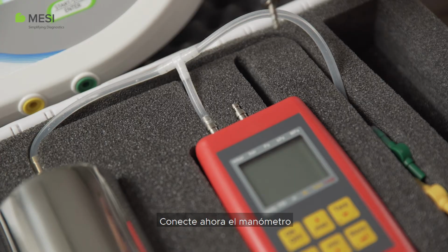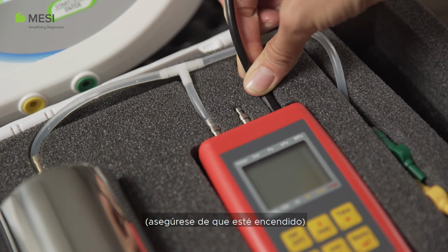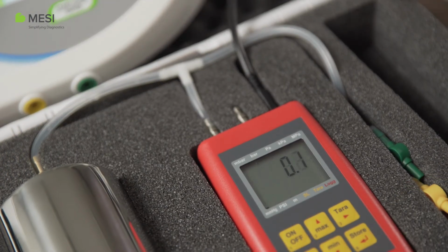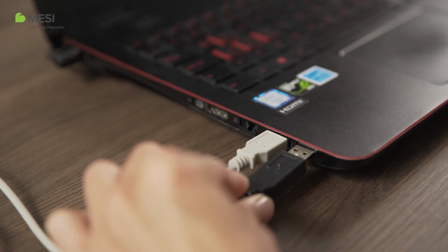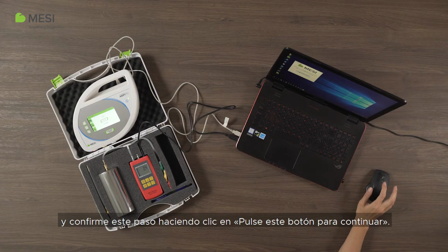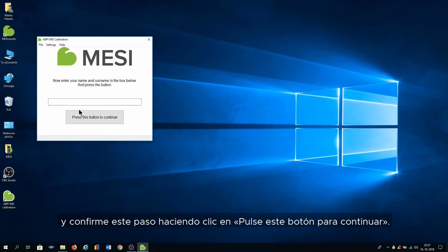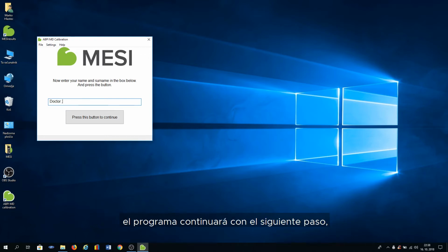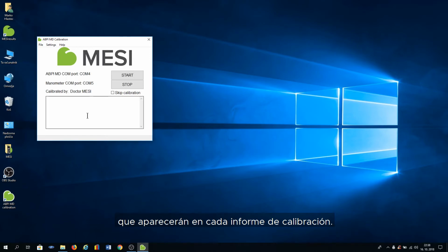Now, connect the manometer. Please make sure it's turned on. And confirm the step by clicking Press this button to continue. If the COM port selection finished successfully, the program will go to the next step, where you enter your name and surname that will appear on each calibration report. You're now ready to calibrate your device.